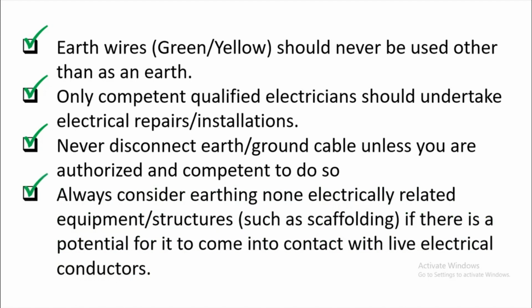Always consider earthing non-electrically related equipment structures such as scaffolding if there is a potential for it to come into contact with live electrical conductors. When you find that there are overhead power lines or the scaffolding is near the power lines, don't immediately engage on that job inside of the scaffolding. First, you need to check if it is connected to or touching the electrical system, because it might be electrified and you will get an electrical shock when approaching the scaffold. So always make sure those scaffoldings and any related platforms are not energized or in contact with the electrical system, to make sure that you will not get an electrical shock.